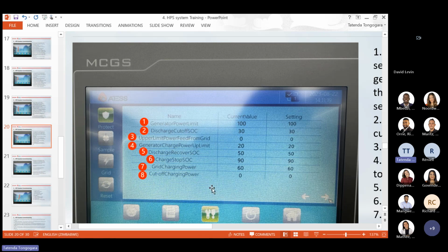And then we also have our grid charging power. This is the power that you want your batteries to charge from grid. So your grid limit could be 100, but you only want to charge with 20 kilowatt from grid. You don't want to charge with a lot of power from grid. You can set this value. You can even set it to 0 if you don't want to charge with grid.